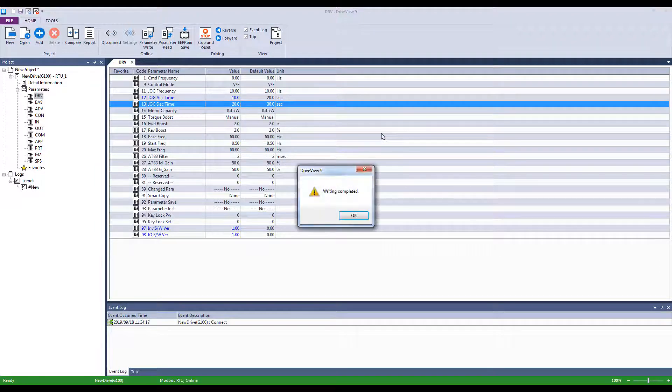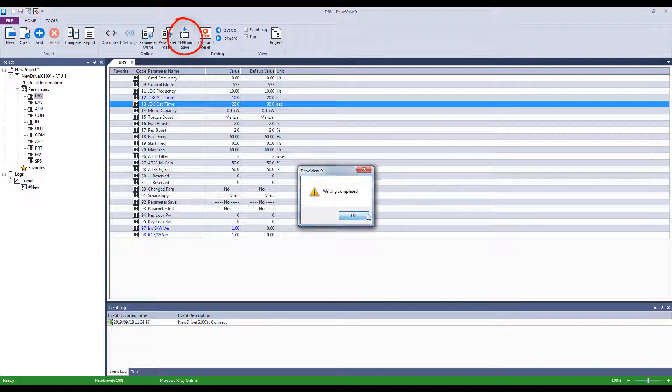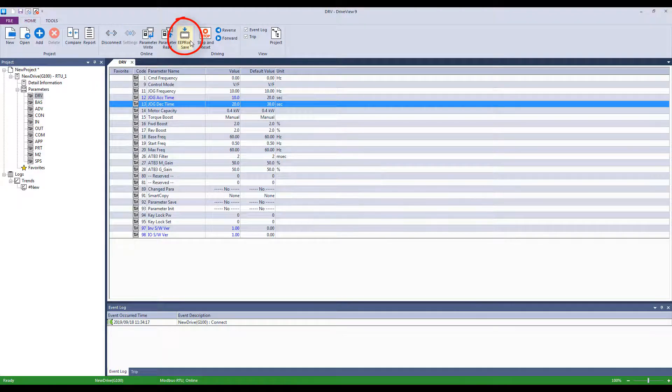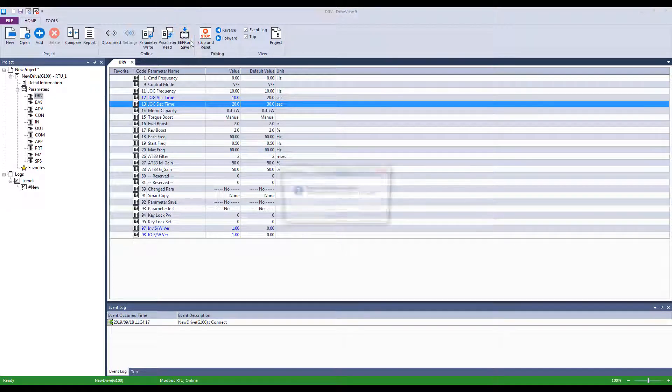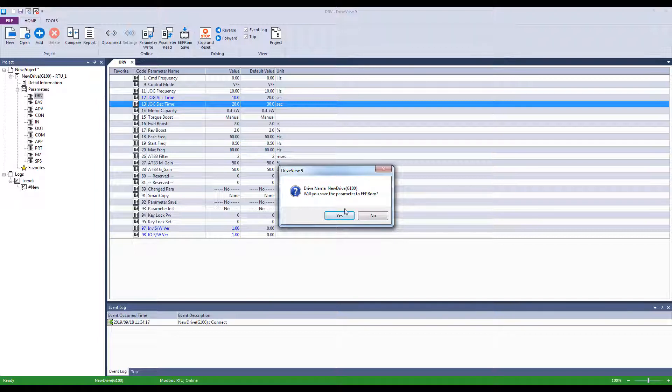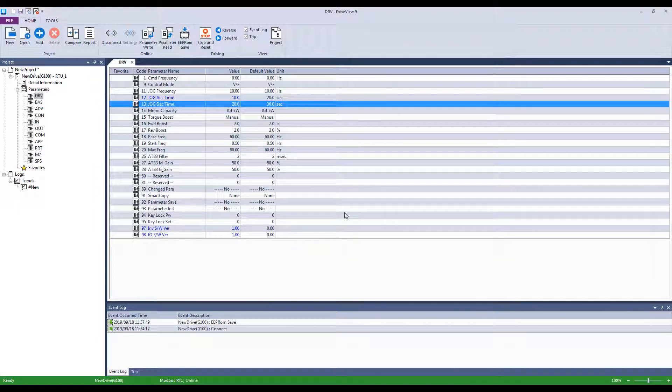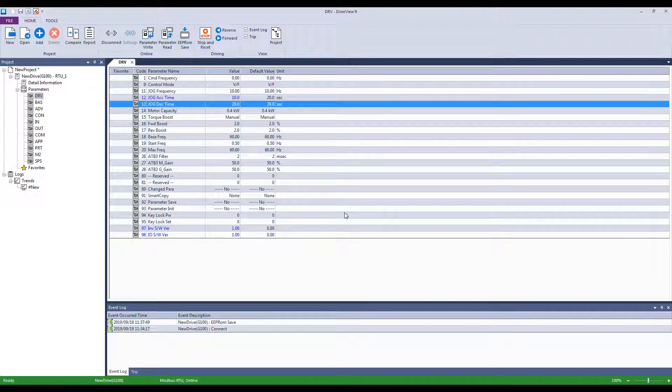Once you change and write all the various parameters, it is important that you click the EEPROM button. This button will save the parameters to non-volatile memory so that the changes will still be there after a power cycle to the drive. If you do not click the EEPROM button, you will lose all the parameters once the VFD loses power. After you have set your desired values, you should also save the project.